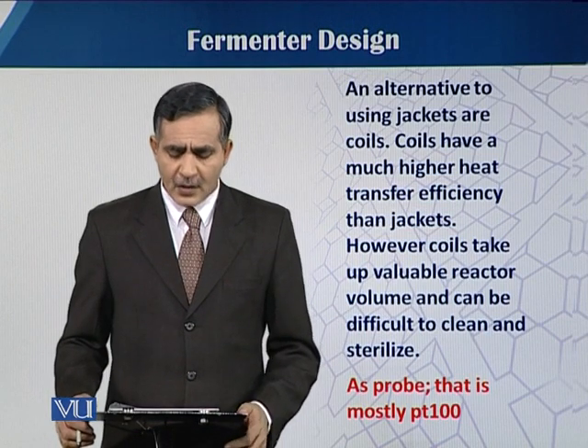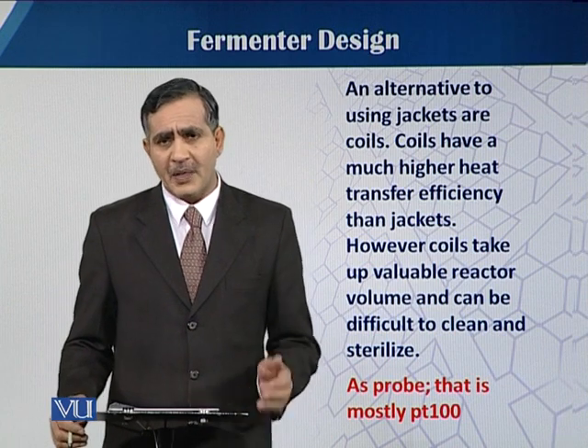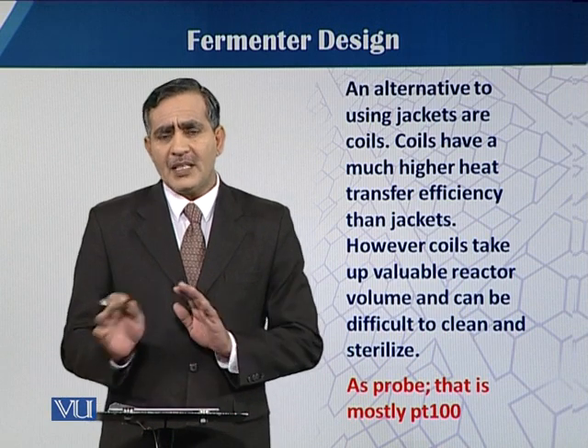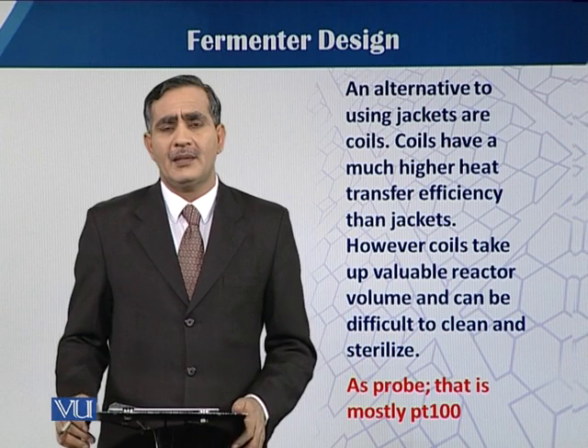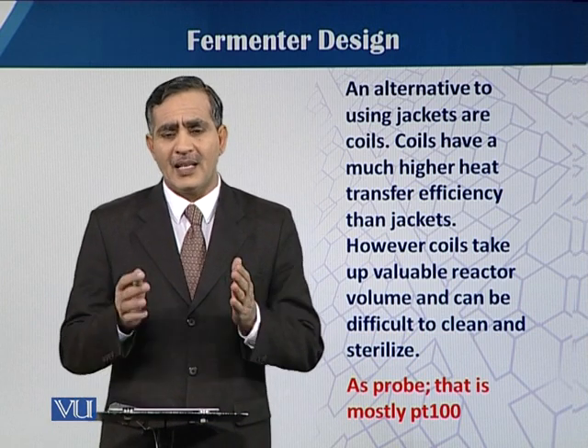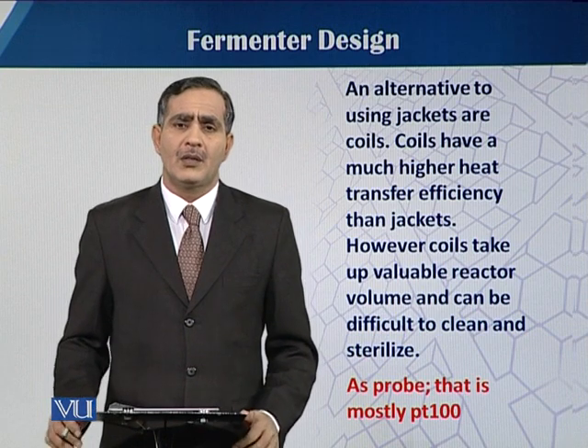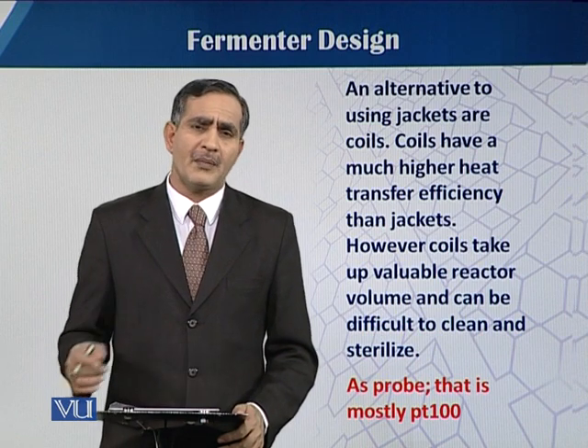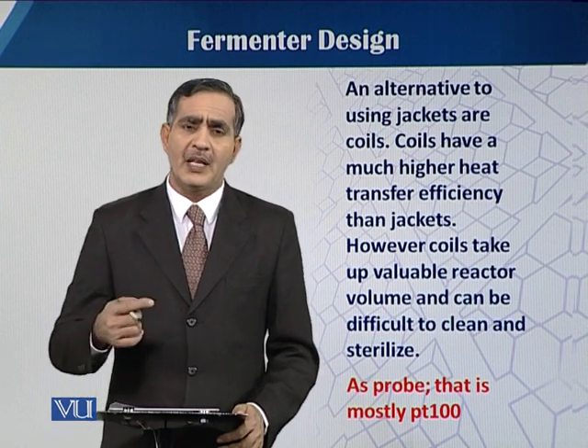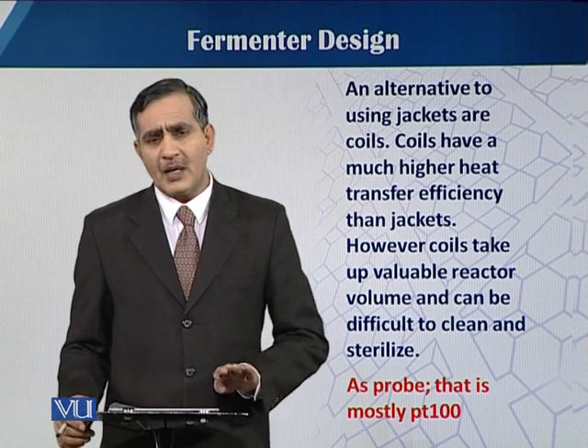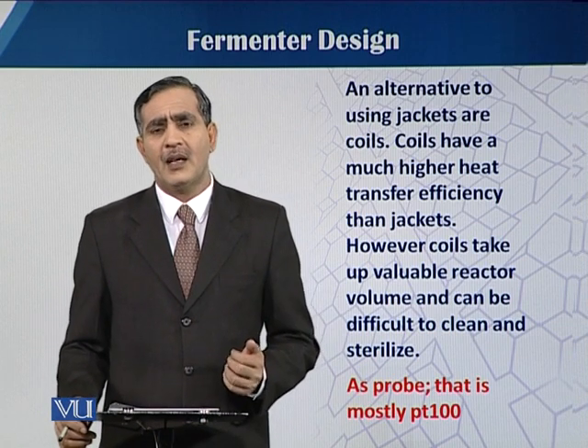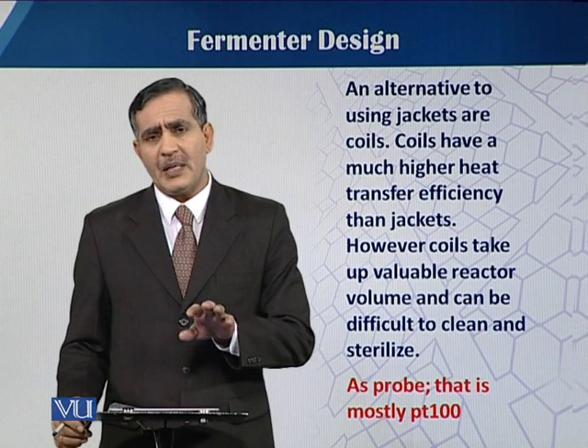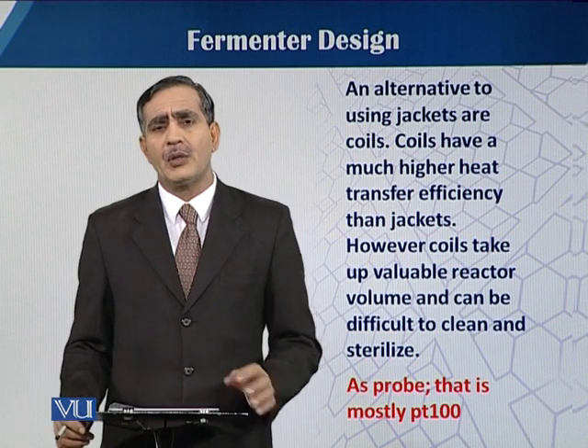As an alternative to jackets, there are cooling coils. The major difference between the jacket and the cooling coil is that when using the jacket there is less surface area. When you use the coil, there is a maximum area available for heat transfer — either from the vessel or from the liquor to the fermentation medium. This is basically one approach to how we can control the temperature.